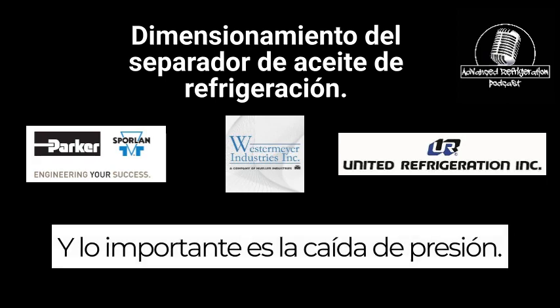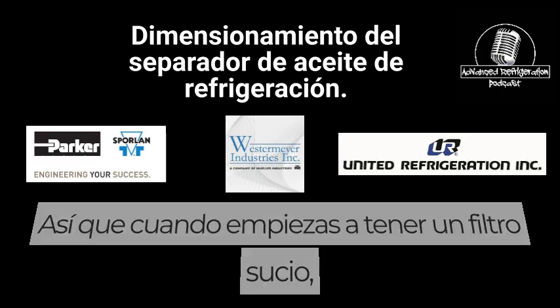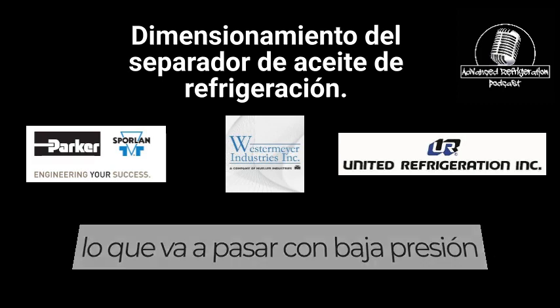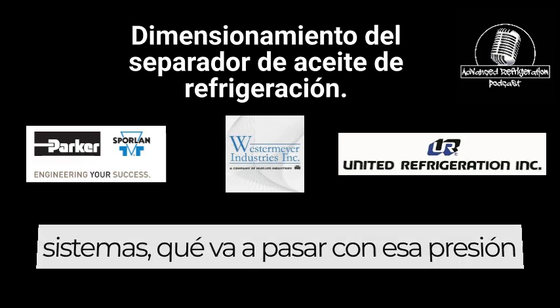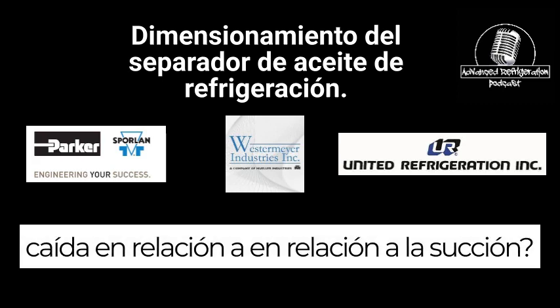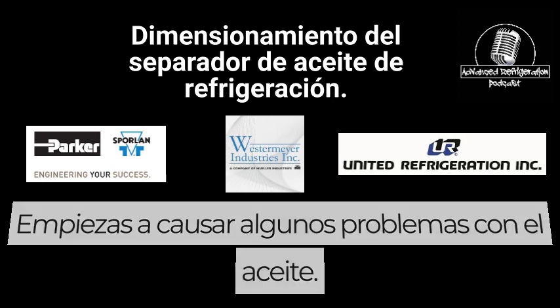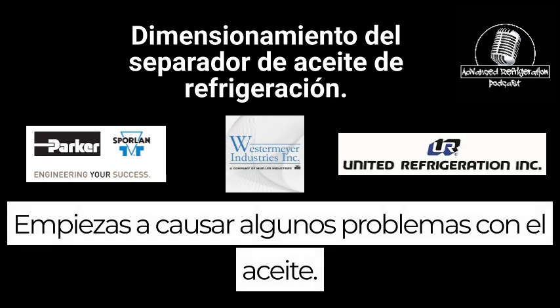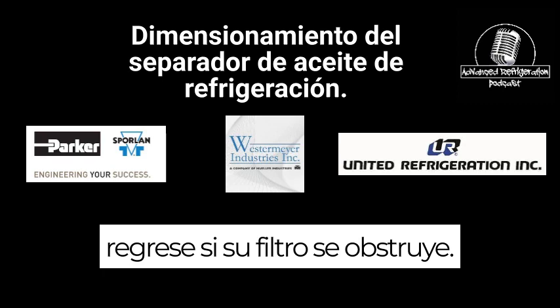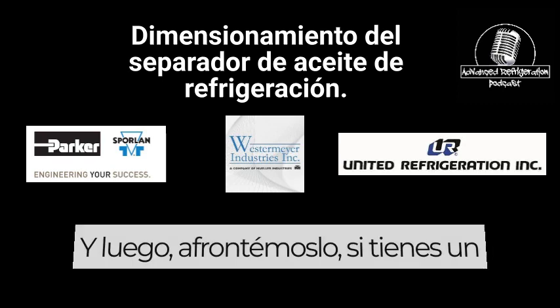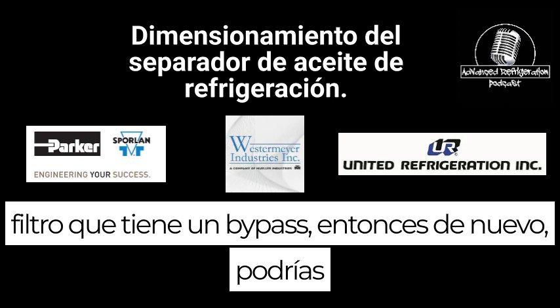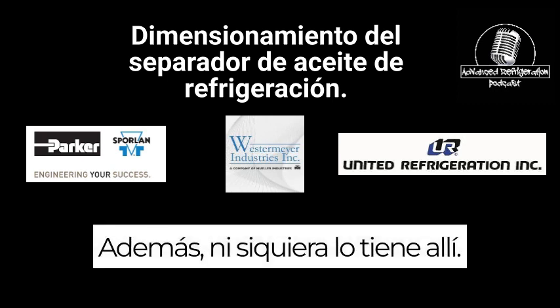And the big thing is pressure drop. When you start getting a dirty filter, what's going to happen on low pressure systems? What's going to happen with that pressure drop in relation to suction? You start causing some issues with oil return if your filter gets clogged. And then let's face it, if you've got a filter that has a bypass, you might as well just not have it in there.